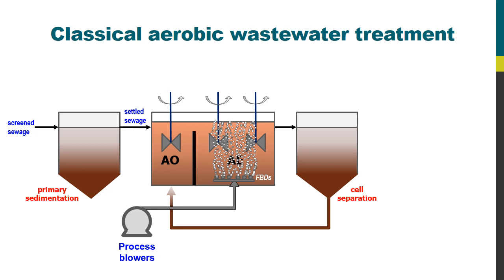The cells are returned to the microbiological tank, normally to the anoxic zone. There are then two waste streams from this process: first from the primary sedimentation process, effectively just the solids from raw sewage, so a little bit smelly, and then the spare cells from the biological tank, normally referred to as waste activated sludge.